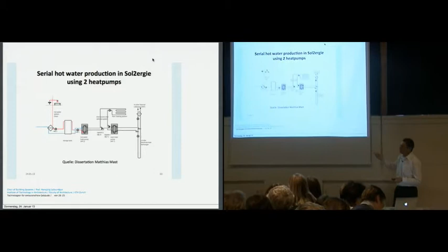So now, knowing this, we have a new kind of hot water production: the heat pump section with the circuit of the hybrid solar collector, the circuit for the earth probe, and the heat pump that shifts energy into the room system. Now we add a new, separate heat pump to produce hot water, taking its source heat out of the return quasi-circuit of the building.